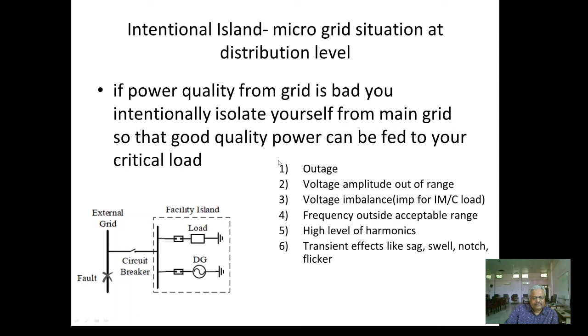If power quality from the grid is bad, you intentionally isolate yourself from the main grid so that good quality power can be fed to your critical load. Also, if an outage takes place, then you intentionally island yourself. Or if the voltage amplitude is out of range from the grid, you intentionally island. These are the reasons why we intentionally island our system.